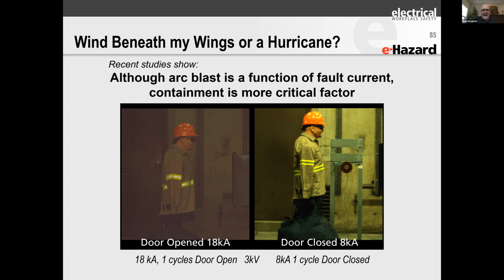The calories do not make pressure. It's the fault current, and it's really a very short period of time that it'll develop pressure. So you can blow a door off a piece of equipment. That's why typically you always operate to the side of the equipment.